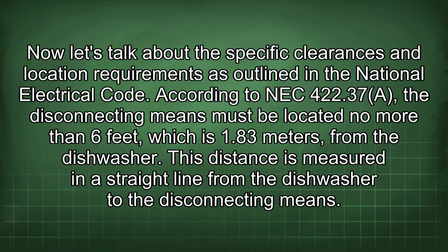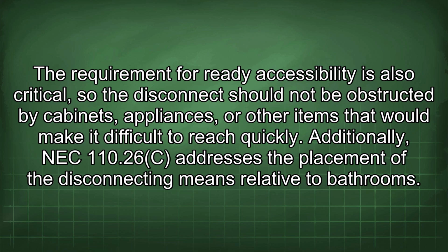Now let's talk about the specific clearances and location requirements as outlined in the National Electrical Code. According to NEC 422.37a, a disconnecting means must be located no more than 6 feet, which is 1.83 meters, from the dishwasher. This distance is measured in a straight line from the dishwasher to the disconnecting means. The requirement for ready accessibility is also critical, so the disconnect should not be obstructed by cabinets, appliances, or other items that would make it difficult to reach quickly.